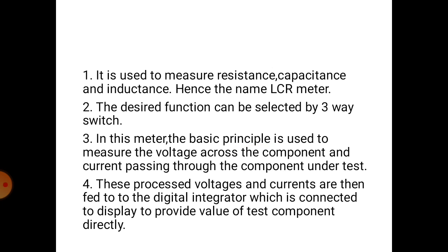It is used to measure resistance, capacitance and inductance, hence the name LCR meter. The reason why it is called LCR meter is L stands for inductance, C for capacitance and R for resistance. Since it is used to measure all the three values, it is called LCR meter. The desired function can be selected by a three-way switch.